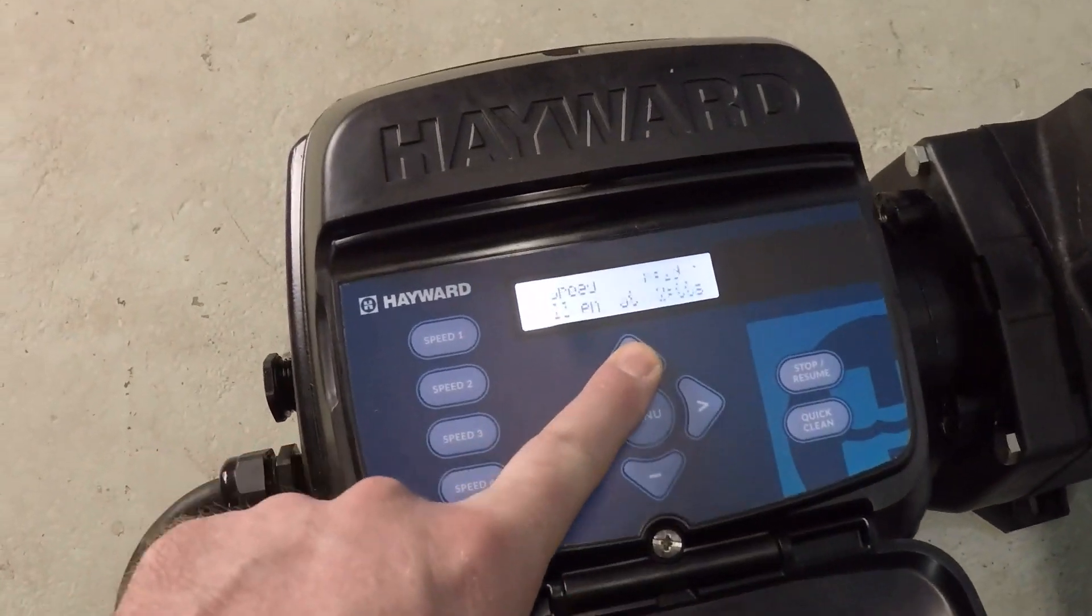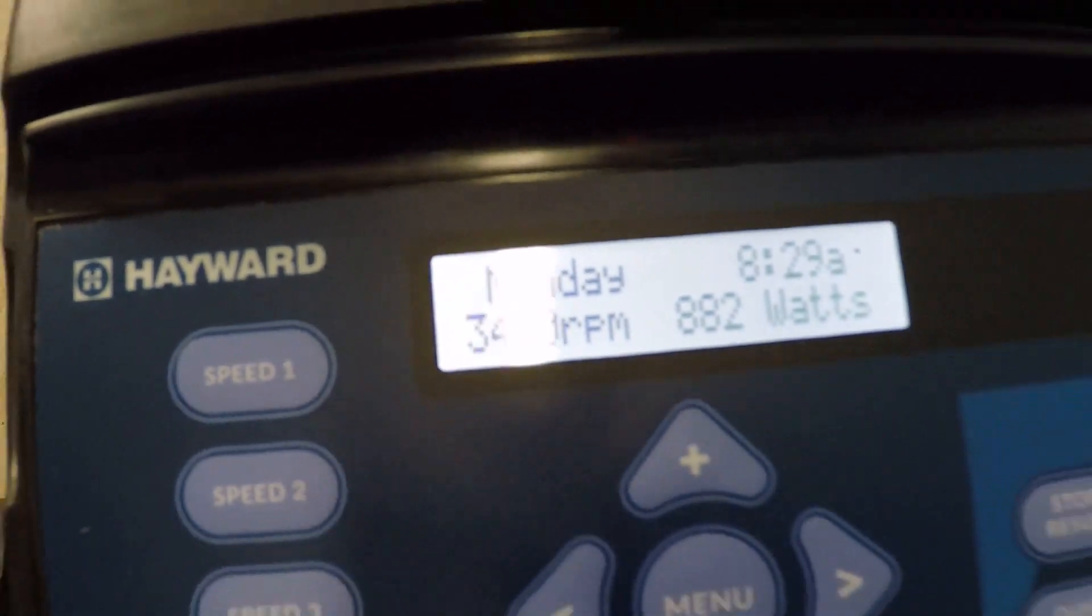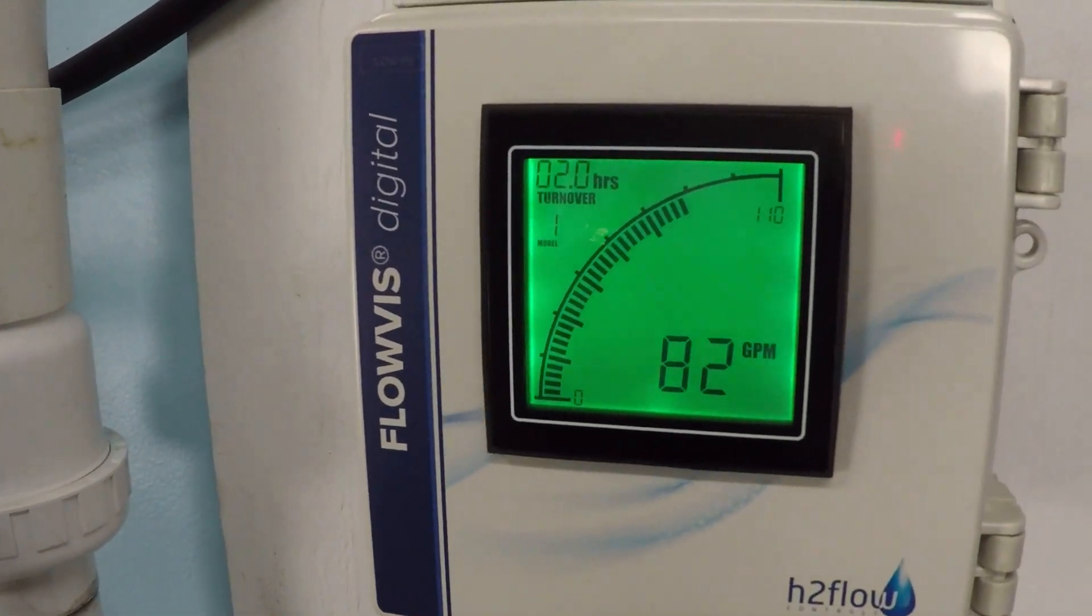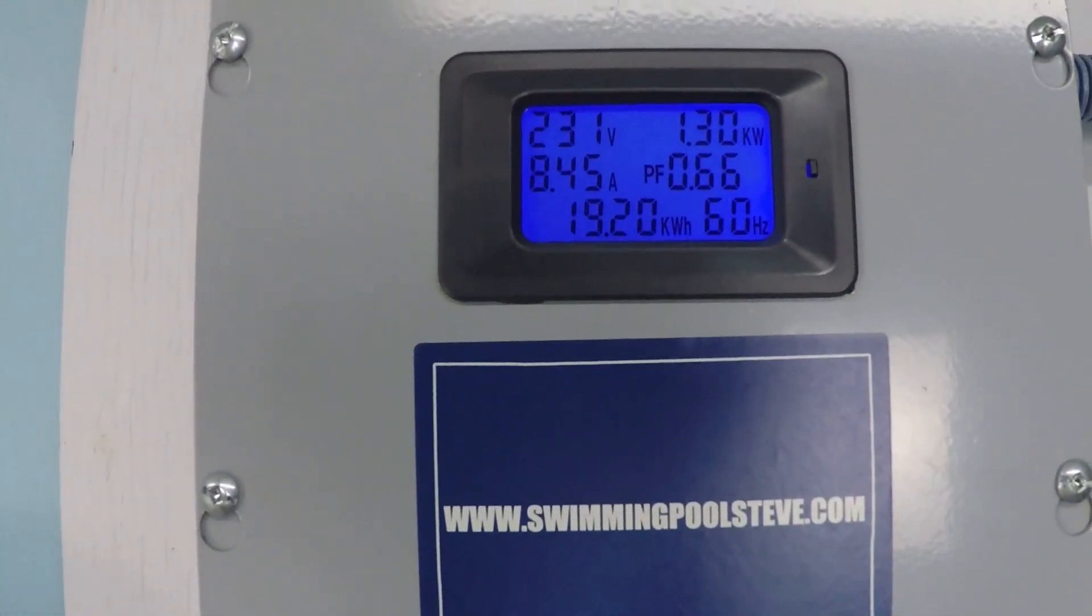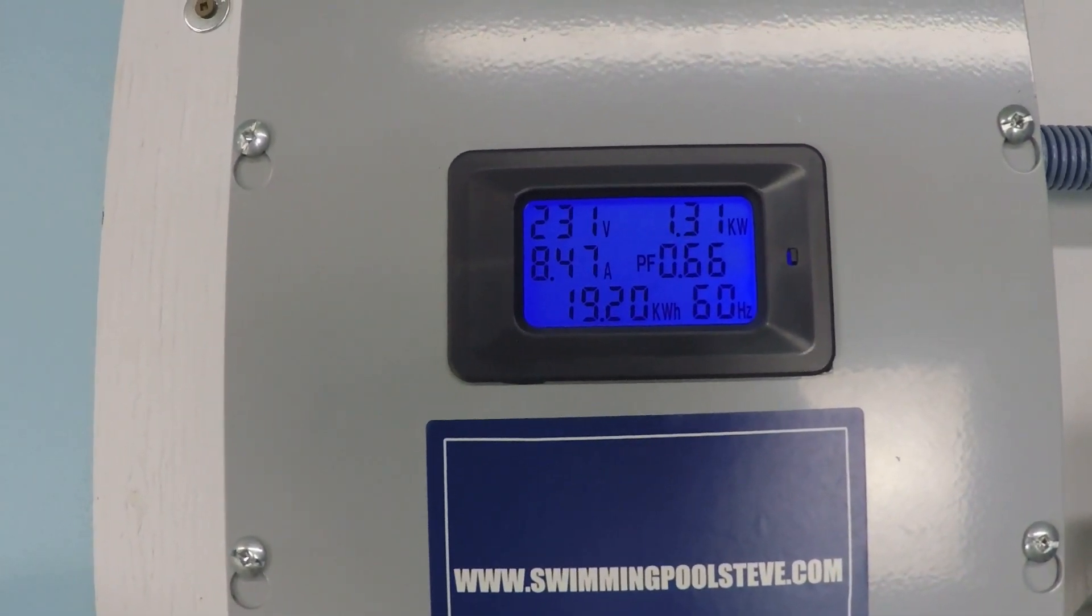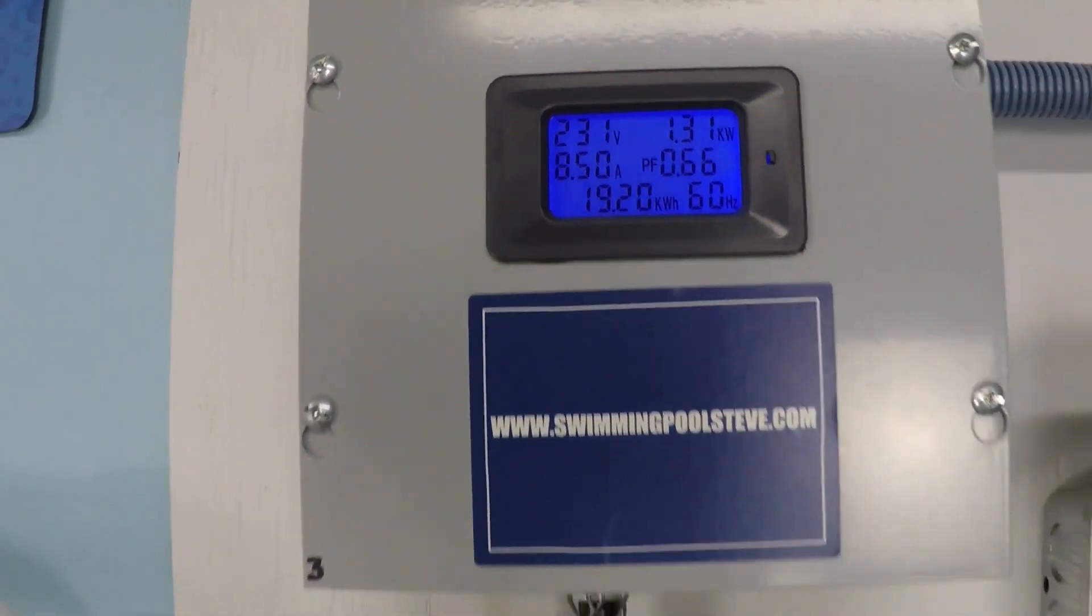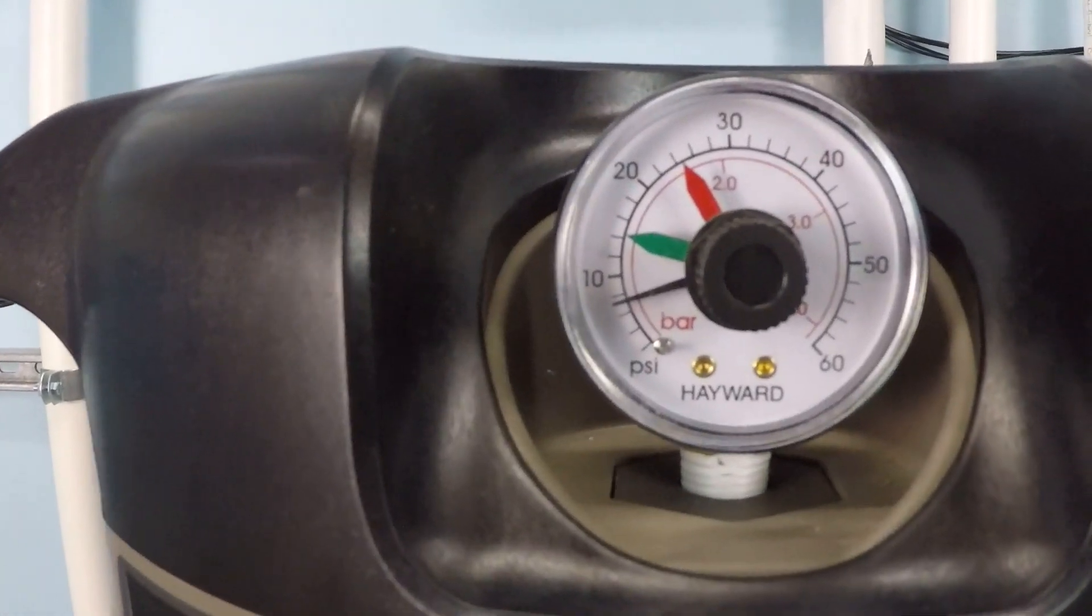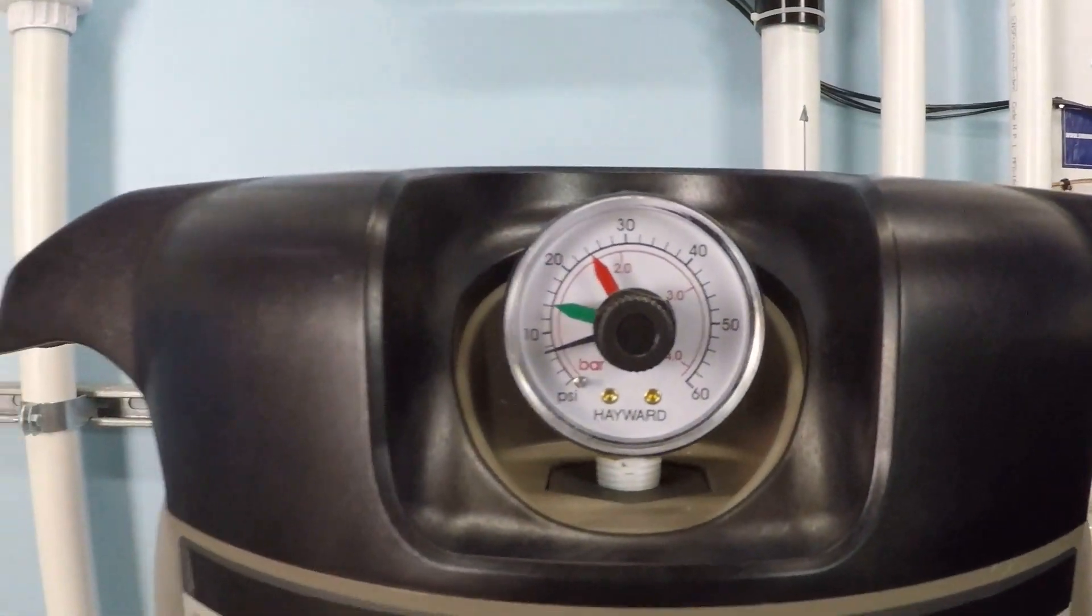And this next test will be maximum speed. 3,450 RPM. 83 gallons per minute. 1.3 kilowatts, 1,310 watts, and on the left hand side you see about 8.5 amps at 230 volts. Let's take a look at the pressure here. About 8.5 psi.